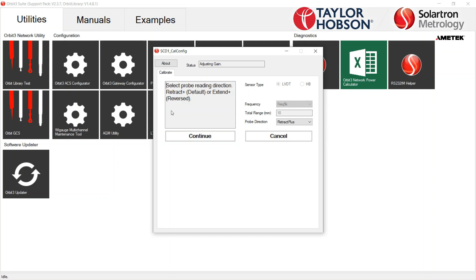The next step you can take is now the validation of the calibration you just did. This is where you can actually just take a live reading and see if this matches up to what you want to have. If you wish, you could just click Finish, go back and calibrate again.